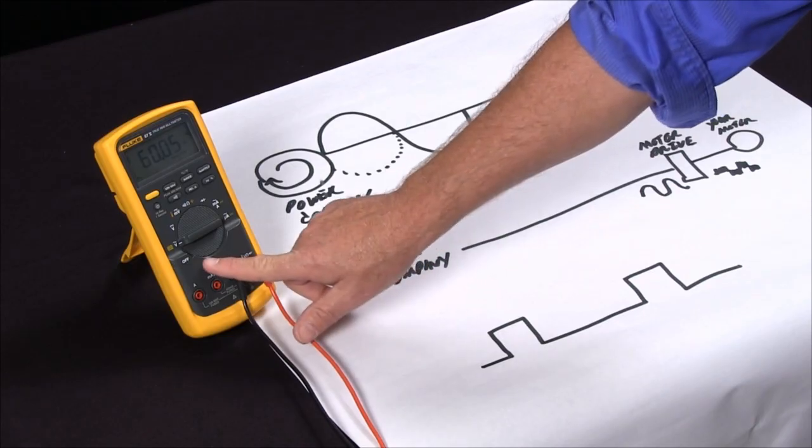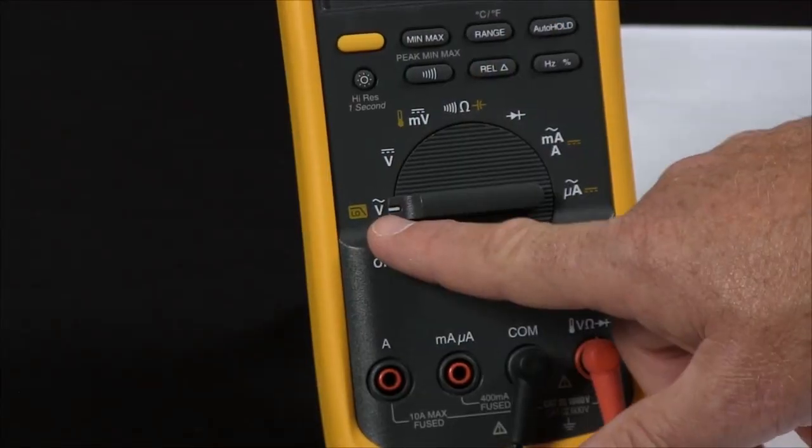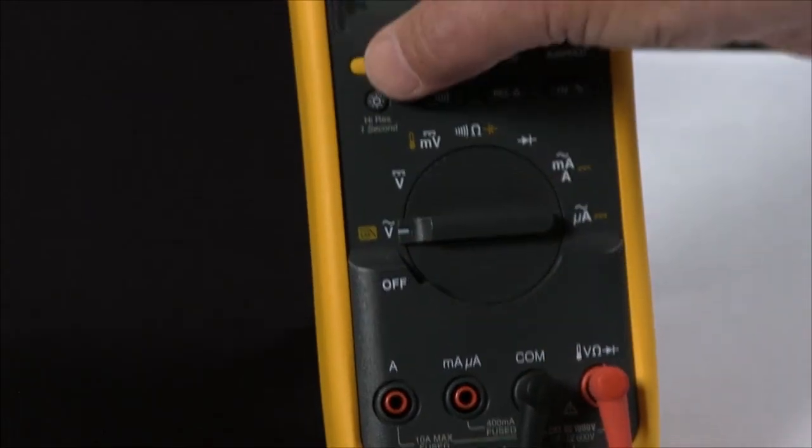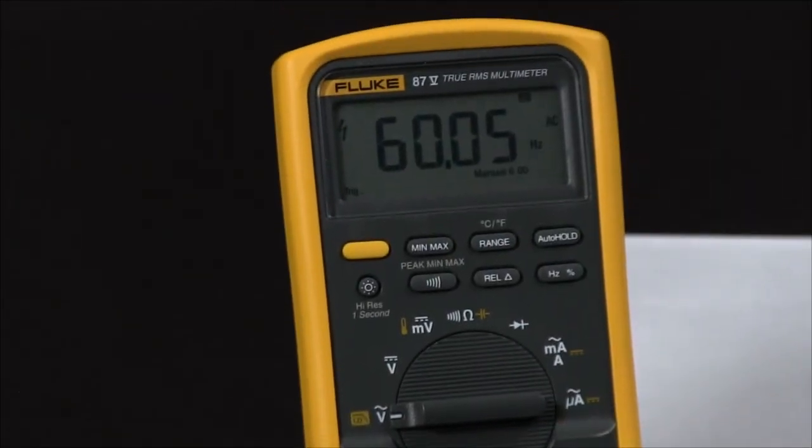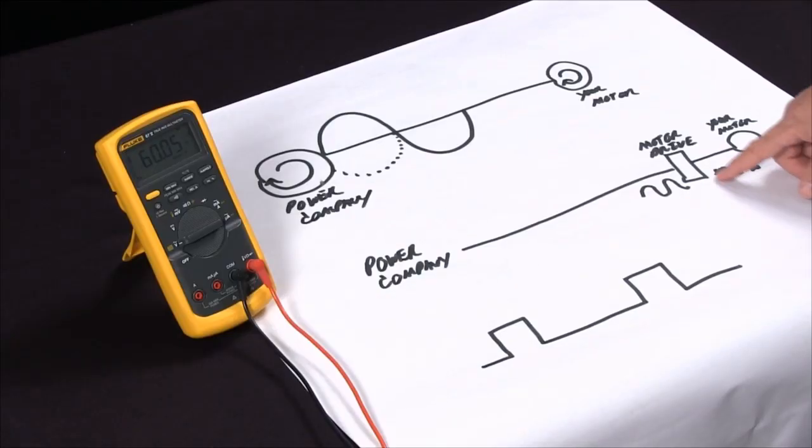We added a feature on the Fluke 87V and our 1587. If you see next to the AC volts, there's a low pass. By hitting this yellow button, I've now converted this into a special measurement mode that will measure this pulse width modulated signal accurately, giving you the frequency.